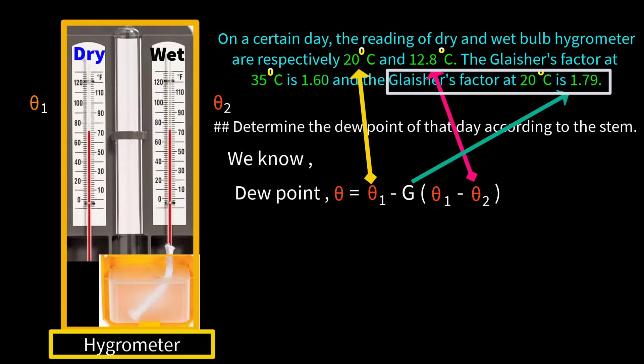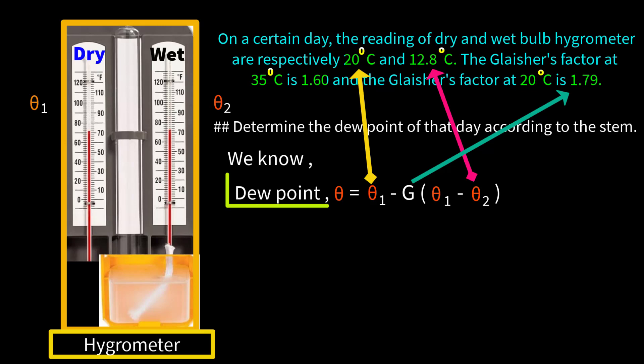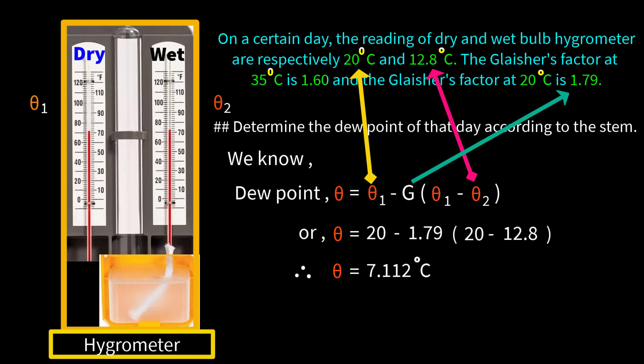The value of G is always taken based on the temperature reading of the dry bulb thermometer or air temperature. Now applying Glaisher's law: θ = 20 − 1.79 × (20 − 12.8). Therefore, θ = 20 − 1.79 × 7.2 = 20 − 12.888 ≈ 7.112°C. This is our final answer.